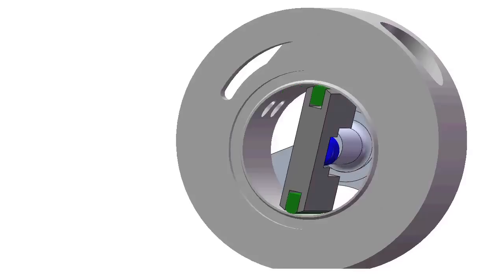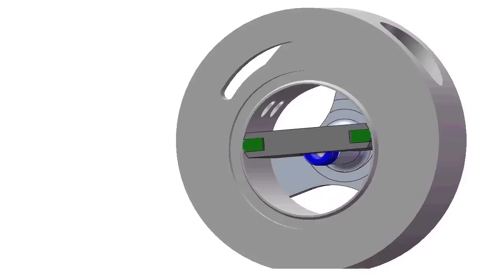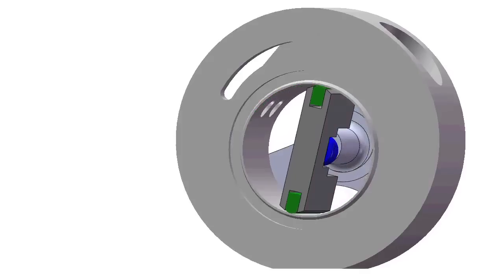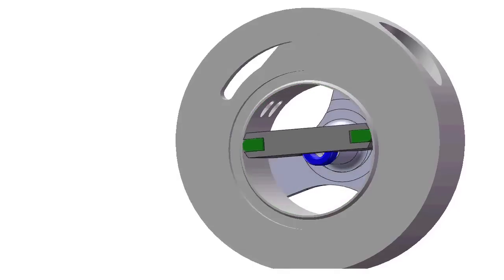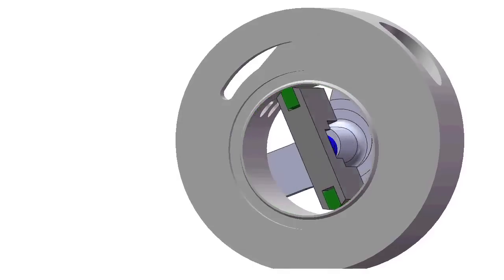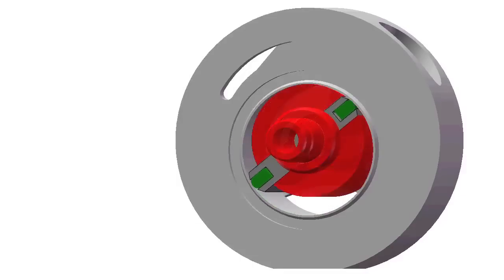The Eccentric Cam provides additional benefit by removing sliding friction from the fluid chamber, reducing fluid heating, which improves the compressor's isentropic efficiency. This is one of the key elements that allows the compressor to scale across a large capacity and speed range.